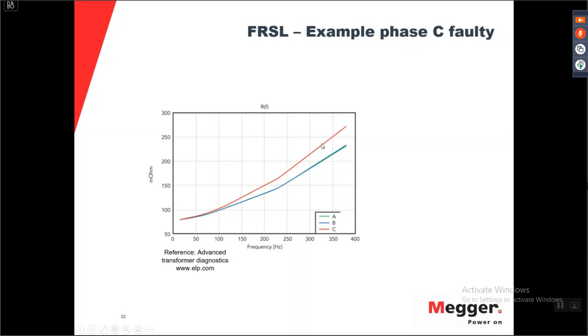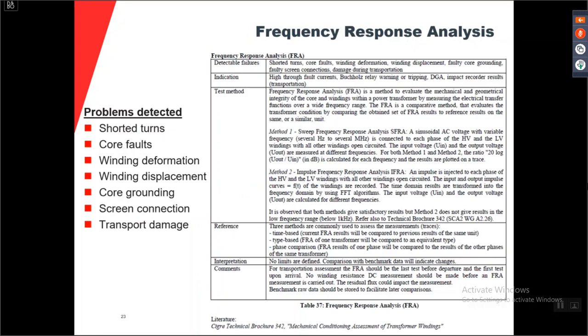And do you remember what the criteria was? Here, it should not be a bigger change in the resistance of 15%. So this is what you're looking for in the FRSL test. Frequency response of stray losses. When we talk about frequency response of stray losses, it is very often confused with the FRA test, the frequency response analysis test. That is a completely different test, which is the next test in the advanced test of the transformers.